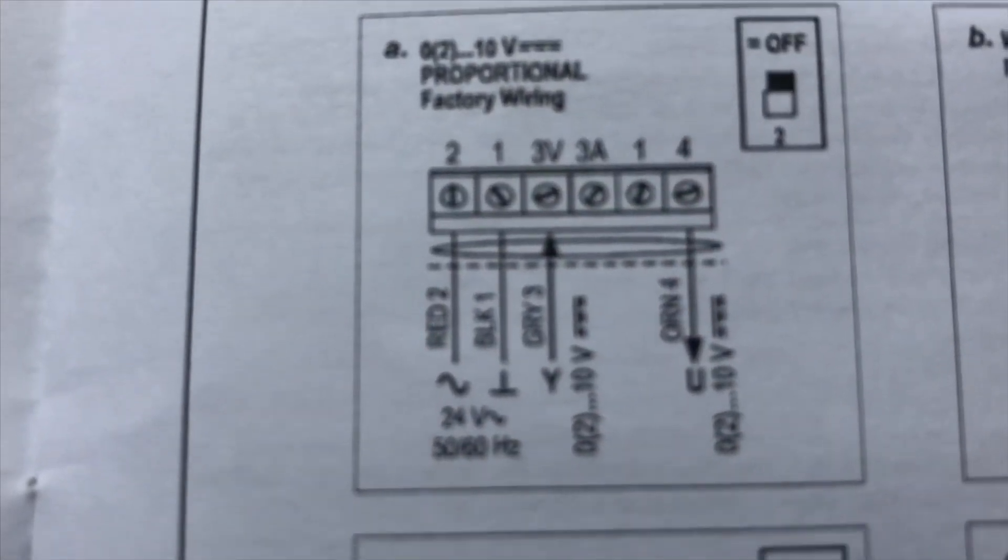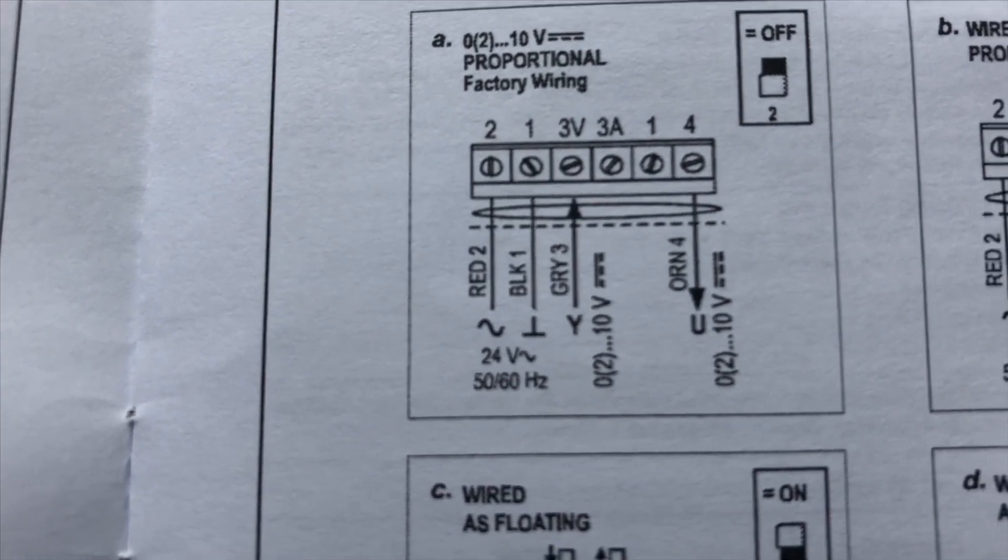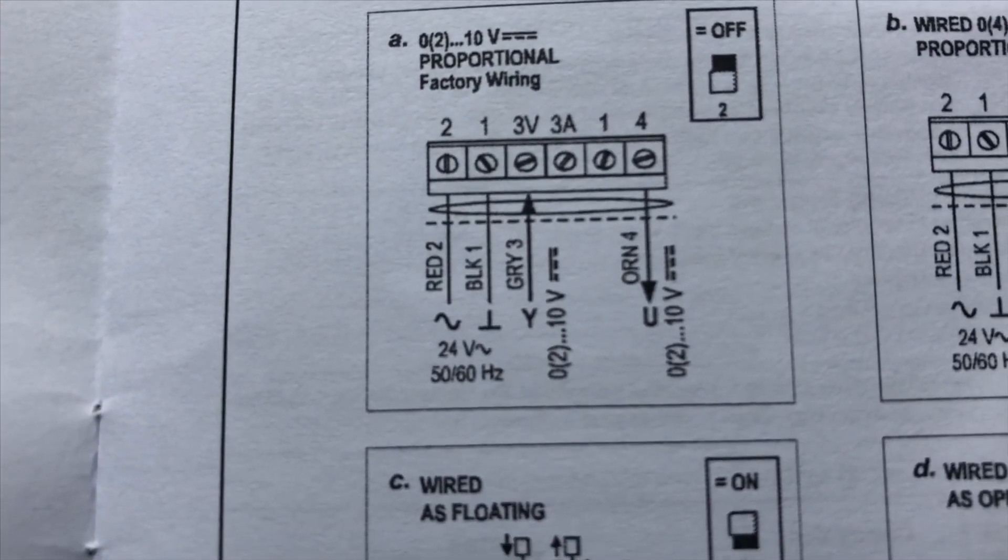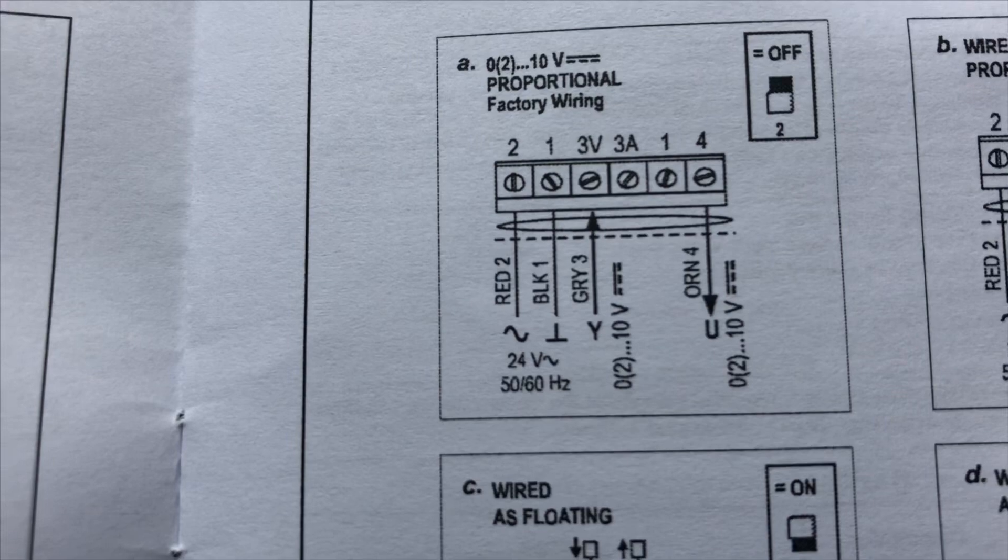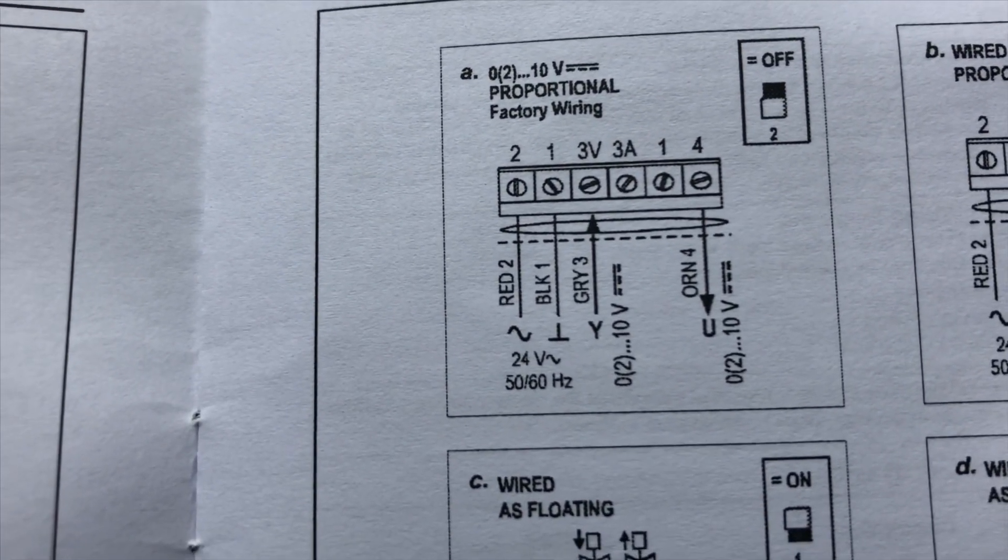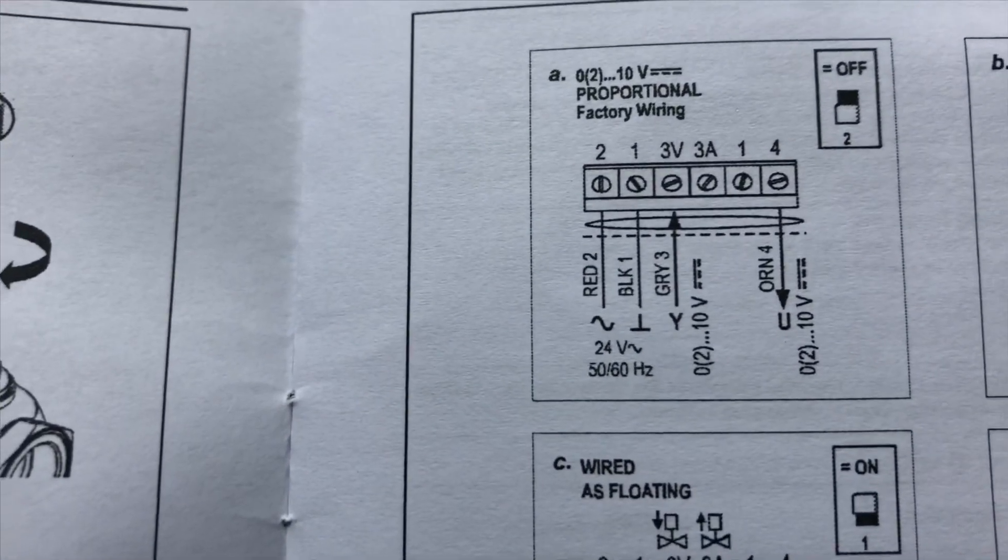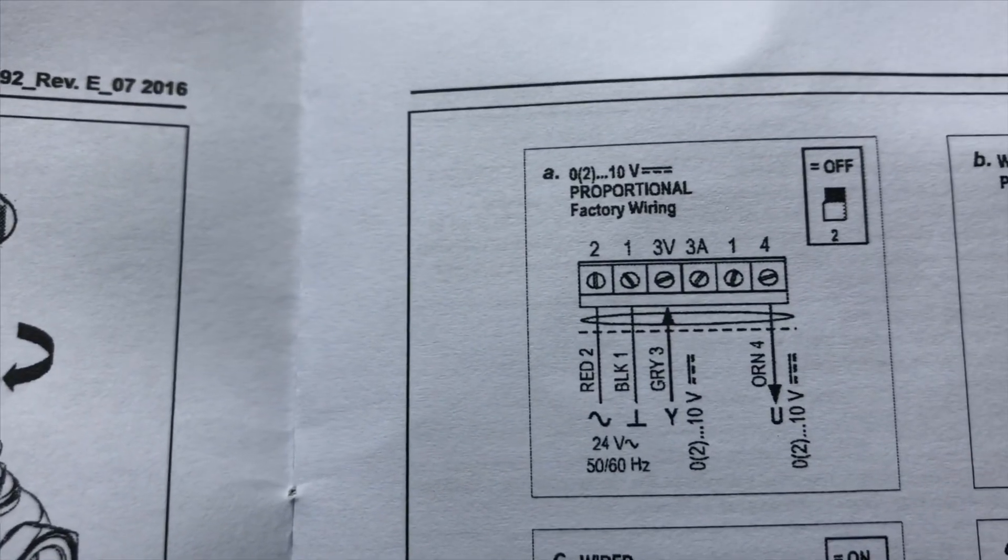Using the existing ArmorFlex, we're using our factory wiring, how the actuator is wired from the factory. Our red wire for our new actuator is our 24 volt. Our black is our ground or common. And our gray is going to be our 0-10 VDC wiring, which is our control wire.